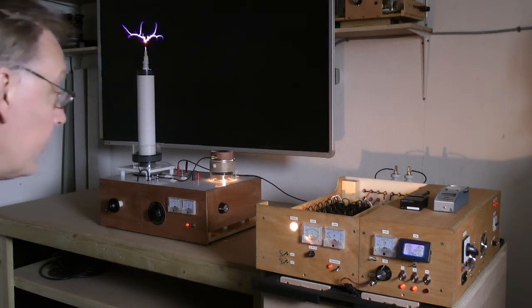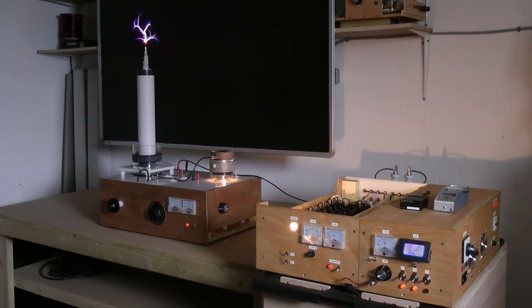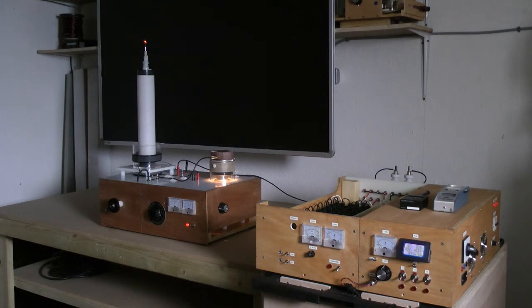We're consuming about 13 amps, 17.2 volts. Obviously its apparent power is different, power factor 0.47, it's CW. Okay, give the system a little bit of a chance to rest, and now I've seen everything working together, I'm going to move the camera into closer proximity to the discharge, so we can actually look at the discharge itself.